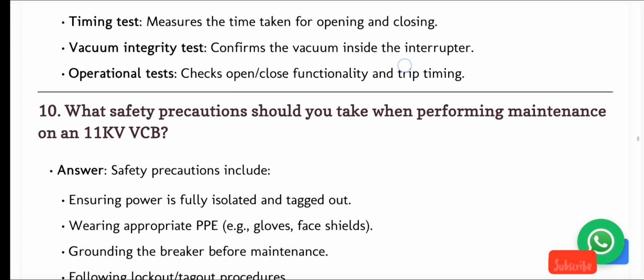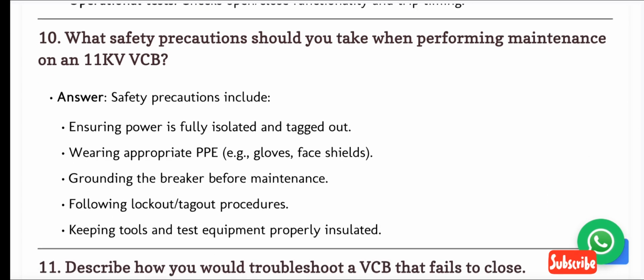10. What safety precautions should you take when performing maintenance on an 11 kV VCB? Answer. Safety precautions include ensuring power is fully isolated and tagged out, wearing appropriate PPE, e.g., gloves, face shields, grounding the breaker before maintenance, following lockout-tagout procedures, keeping tools and test equipment properly insulated.